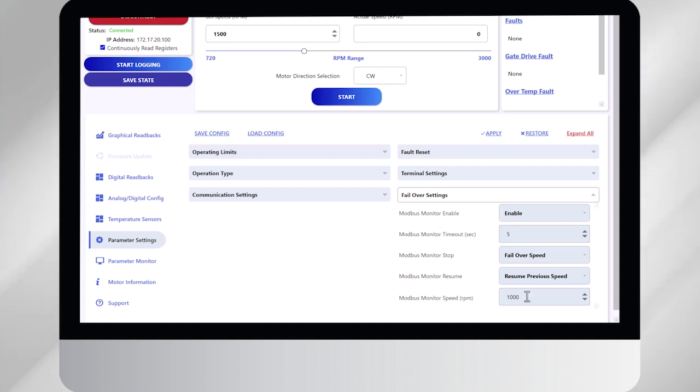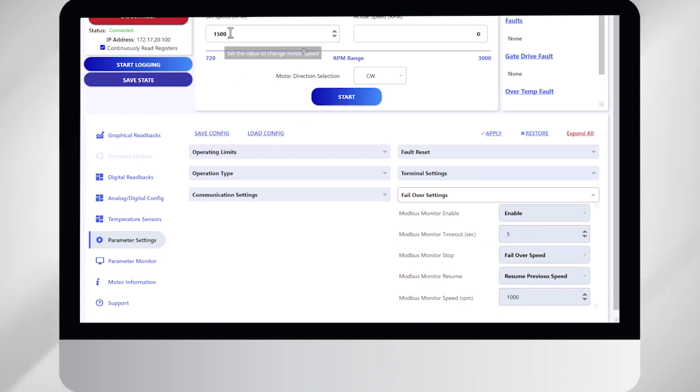And the last button is the speed you want the motor to maintain when it goes into failsafe mode. So after five seconds, in my particular example, it's going to go from 1500 RPM to 1000. Now I'm going to go ahead and start the motor and show you what this looks like.